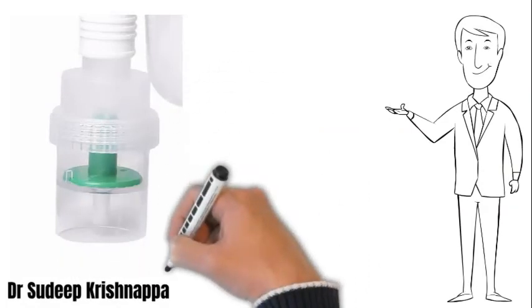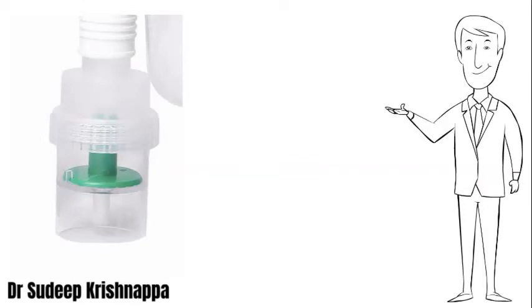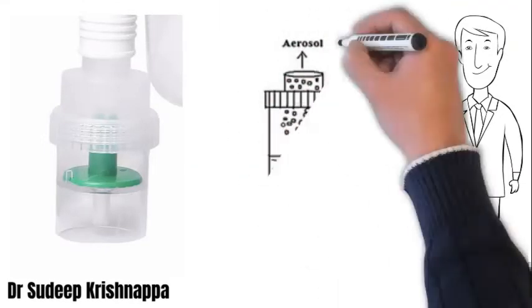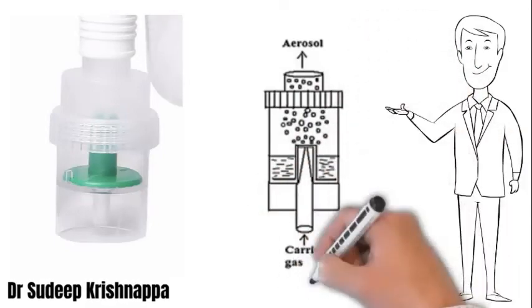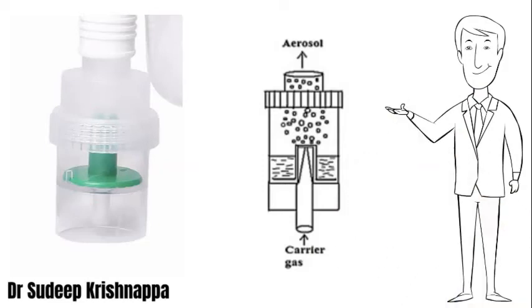In this scenario we have a second make of a Venturi nebulizer — again, only the chamber is highlighted. The line diagram represents the internal functioning mechanism of this nebulizing chamber. Oxygen is led in by tubing at the bottom to an orifice where the Venturi effect generates subatmospheric pressure. Unlike the earlier situation, here we have a cylindrical cap with a flat bottom. This sits congruently on the bottom and the oxygen tubing leading on to the orifice, leaving behind a small gap to act like a capillary tube. As the fluid is suctioned through this capillary tube towards the orifice, the jet shatters the liquid against the baffle to generate the aerosol, which subsequently moves on towards the patient.